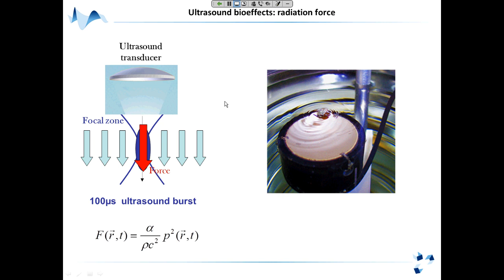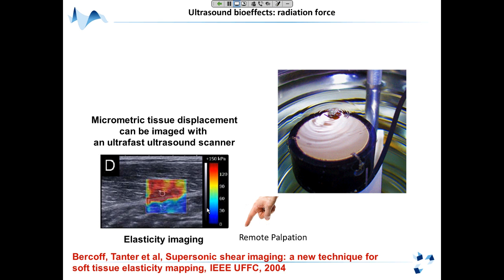And what you see here in water, you would have almost the same in tissues, except that the displacement would be much smaller, a few microns. But those micrometric tissue displacements can be tracked with an ultrasound scanner, and you can reconstruct the elasticity of tissues, as this is equivalent to achieving remote palpation of tissues. It gives you access to the elasticity of tissue. It's a new modality that was introduced a decade ago and is now implemented on some ultrasound scanners, and one commercial scanner is the SuperSonic Imagine device. It's a good example of that.